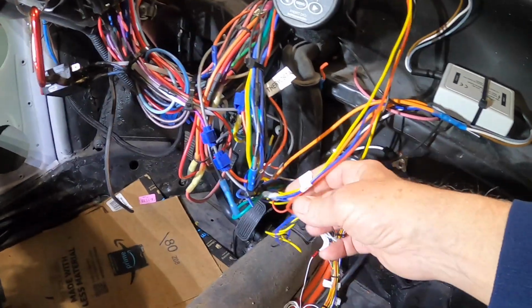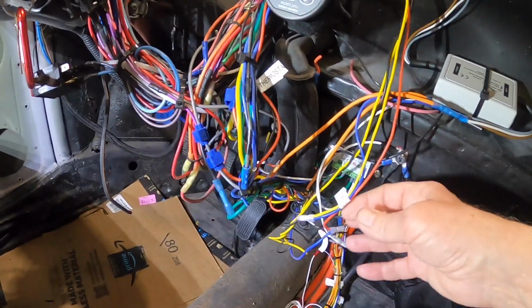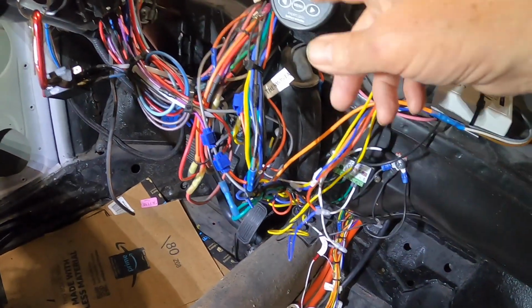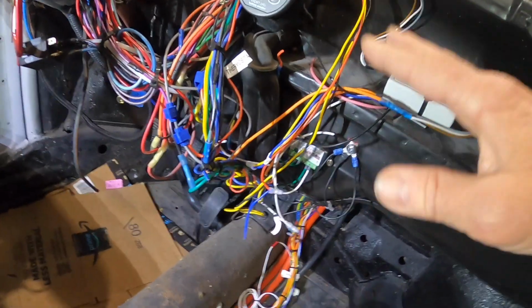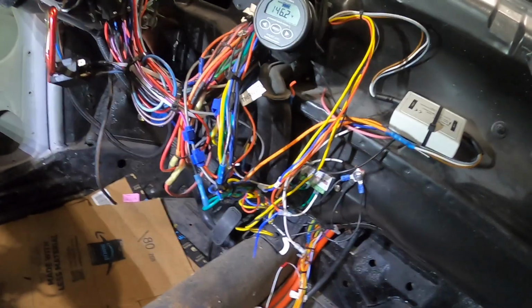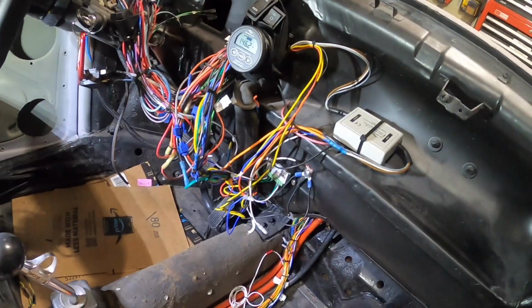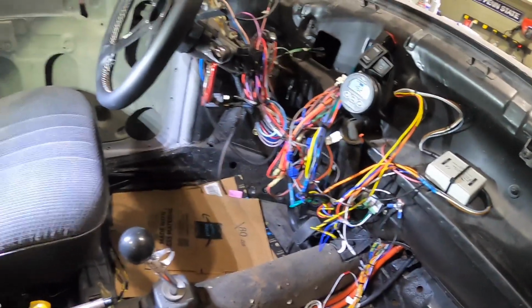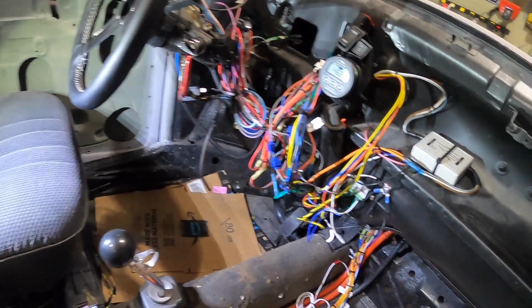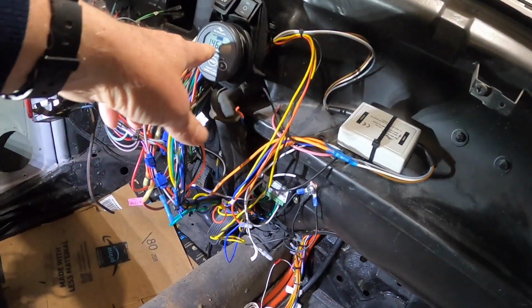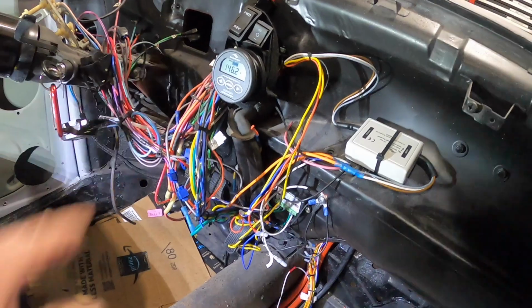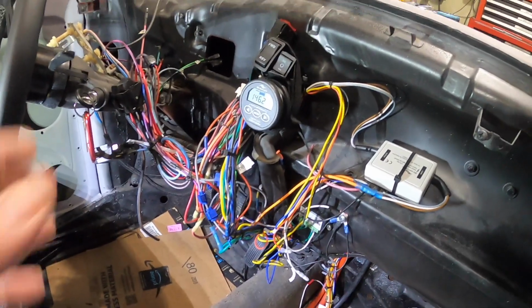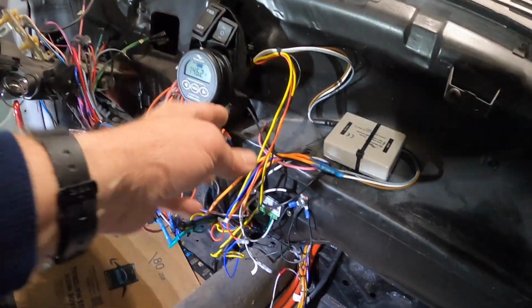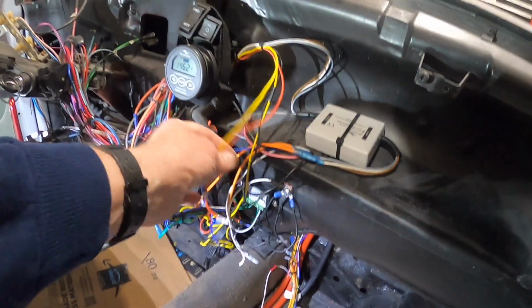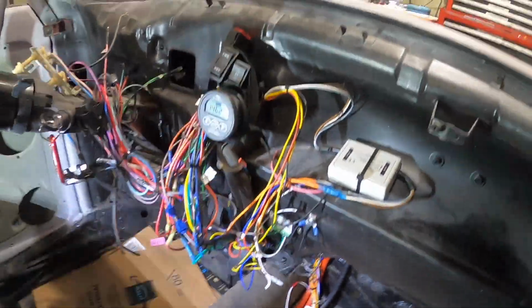My pilot wire is connected in series with the internal relay here as a fail-safe. So if the BMS messes up or the CAN bus signal gets corrupted going to the Elcon chargers, this will be set at a voltage that, if it gets maybe 1.5 volts above where the BMS should be, acts as a fail-safe. It'll open up that relay and turn off the wall charger or public charger. A very easy way of doing it.